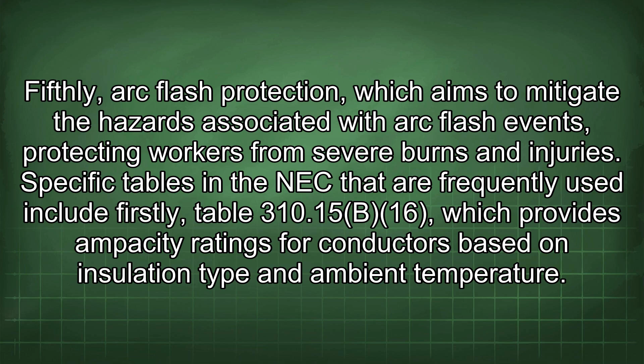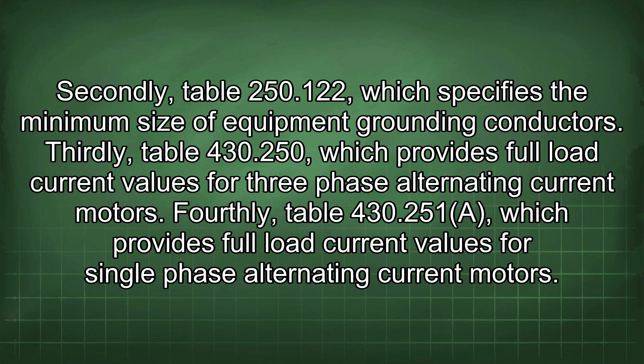Specific tables in the NEC that are frequently used include firstly, Table 310.15(B)(16), which provides ampacity ratings for conductors based on insulation type and ambient temperature. Secondly, Table 250.122, which specifies the minimum size of equipment grounding conductors. Thirdly, Table 430.250, which provides full load current values for three-phase alternating current motors. Fourthly, Table 430.251(A), which provides full load current values for single-phase alternating current motors.